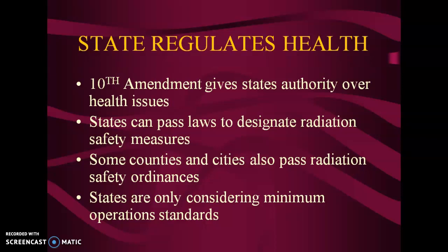Counties can add additional ordinances to that, but they can't do anything that would reduce the amount of regulation. So if the state says that your equipment has to be inspected every 2 years, a county can't come in and say it only has to be inspected every 5. They can't diminish the state's rule, but they could add to it. They could say that it had to be done once a year. So they can make tighter restrictions, but they can't make broader restrictions.